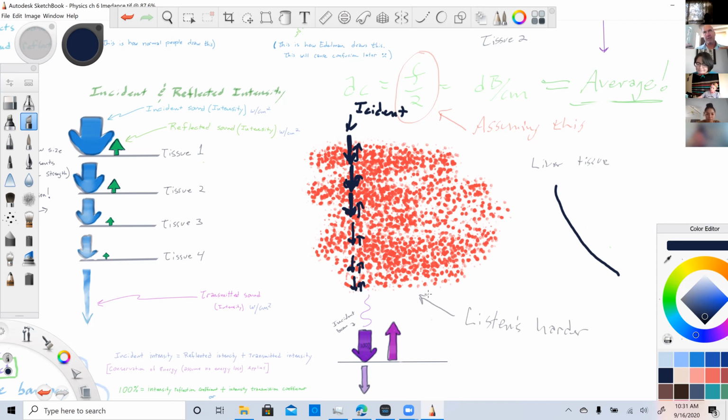So in order to create a smooth image from top to bottom, and not one that goes from bright to very dark, the machine, every microsecond of time that passes, which is the same thing as saying every few millimeters of depth, it listens harder. Another microsecond passes, it listens harder. Another microsecond passes, it listens harder. And it keeps doing that in order to create a steady or a consistent screen.